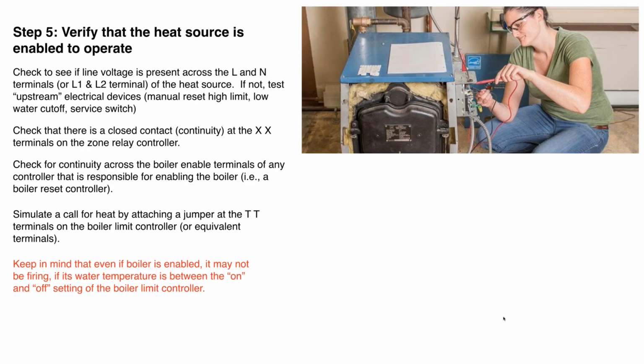Keep in mind that even if the boiler is enabled, in other words, let's say we've put that jumper on TT and nothing's happening. Well, maybe the water temperature in the boiler is between some high limit setting and some differential that the boiler has to cool down through before that burner will start again. Okay, so just because we've enabled the boiler doesn't guarantee that at that moment that boiler is going to fire. All right, that's why we use the term boiler enable.